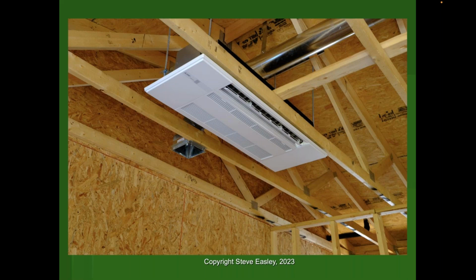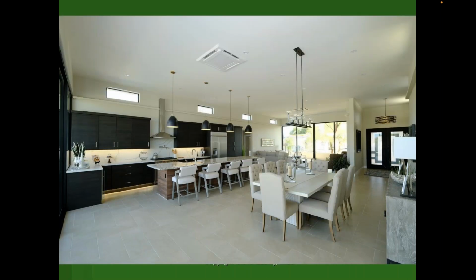This one-way cassette, as it's called here, is manufactured by Mitsubishi. This actually pushes air across the room. It can move air as far as 30 feet. And it has a vane that can direct air up and down, and another vane inside that you can't see that can move the air left or right. So you have tremendous ability to circulate air and provide conditioned air where you want it.